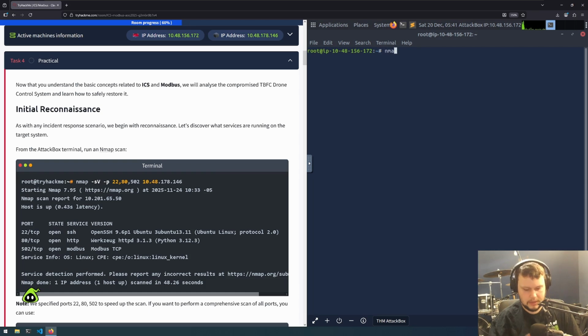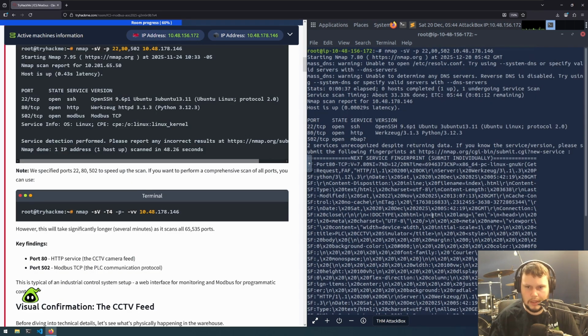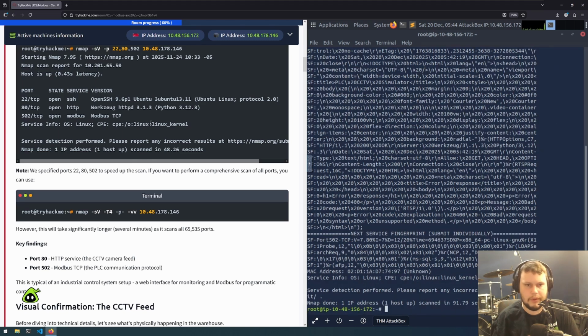So nmap -sV, searching on ports 22, 80, 502, against our virtual machine IP address, and we'll run nmap. Okay, it finished running, and we can see port 22 is open with SSH, port 80 is open with HTTP, and port 502 is open showing MBAP. It appears not 100% sure what's running, though it's suggesting Modbus.